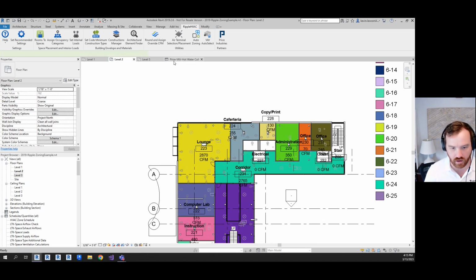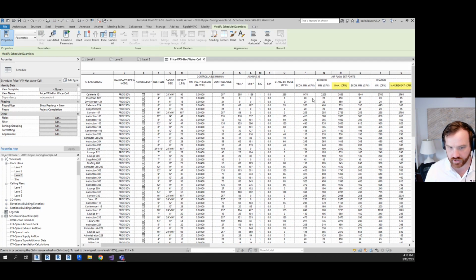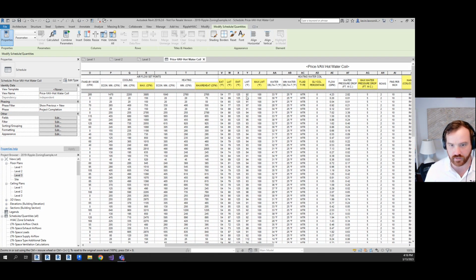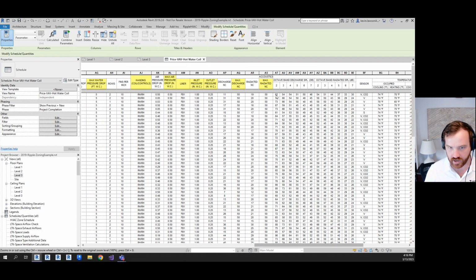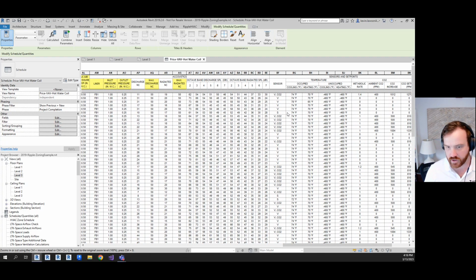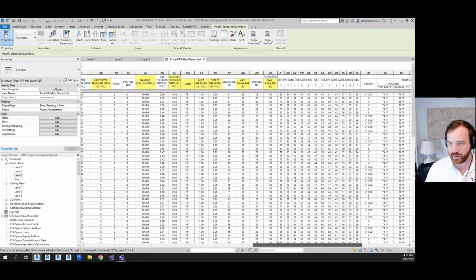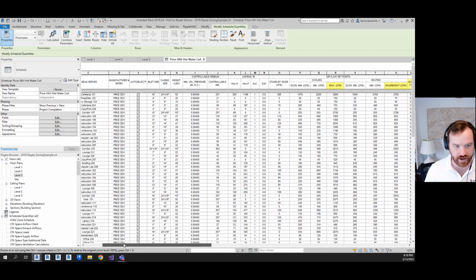It comes with a great VAV schedule. So all of your ventilation calculations get put into the family. Makes real coil selection, so it gives you the real leaving water temperature at the real GPM. Gives you all of the acoustical data you could want, all of your octave bands for discharge and radiated. It selects the sensor based on some of the inputs in the UI, and it pulls some of the set point data out of the space and puts it in the family as well.